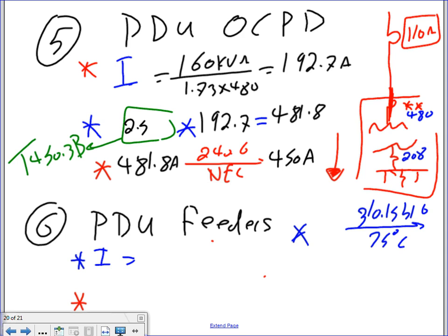Now that's the maximum that you can use. Now, can you use 200, guys? Could you have used 200 or 250? Yes, you can, if the manufacturer comes back and says, we recommend using 250 instead of 450. That's the maximum you can use. Doesn't mean you have to use it. It's the maximum you are allowed to use. Now you can use lower than that.